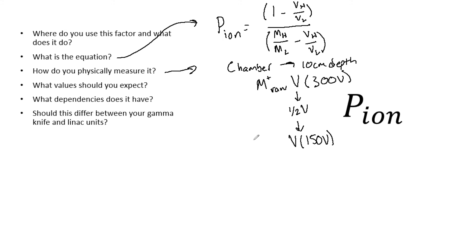Take another reading and this is going to be your M raw minus, and this 150 is our low voltage. So now you have all the readings and measurements necessary. You simply just plug them in to this equation and you find P ion.